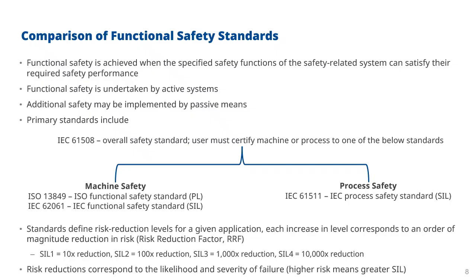If you've got an insurer who's looking at something that's rated as SIL 2, then that's okay, that's a reasonable level of safety. When you go up to SIL 3, then that normally implies that it's much more dangerous and you've had to do a lot more work around making it safe, which also implies that if anything did go wrong, then it would be a lot more dangerous. So there would be cost to the environment, cost to the people, and so on. So higher SIL isn't necessarily better than lower SIL. And this is where the functional safety assessment has to be performed to determine what SIL level is required.